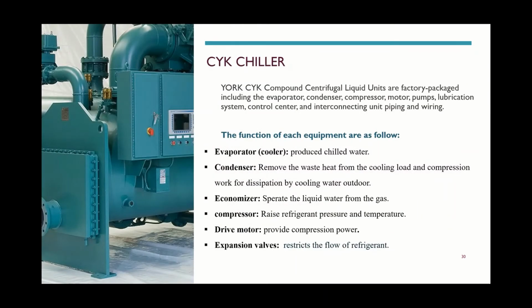York CYK compound centrifugal liquid units are factory packaged, including the evaporator, condenser, compressor, motor, pump, lubrication system, control center, and interconnecting unit piping and wiring. The function of each piece of equipment is as follows. The evaporator or cooler produces chilled water. The condenser removes the waste heat from the cooling load and compression work for dissipation by cooling water outdoors. The economizer separates the liquid from the gas, and the compressor raises the refrigerant pressure and temperature. The drive motor provides compression power. The expansion valve restricts the flow of refrigerant.